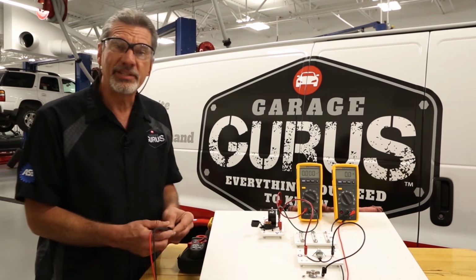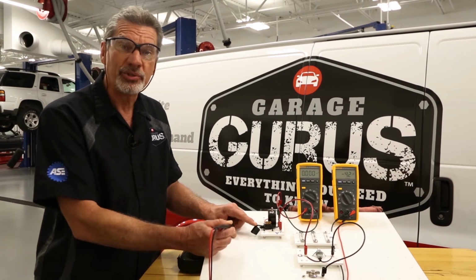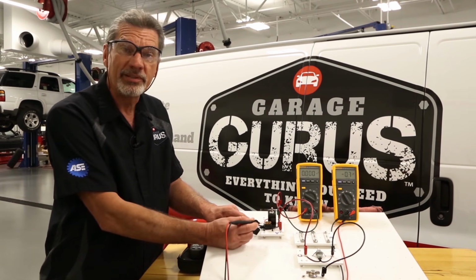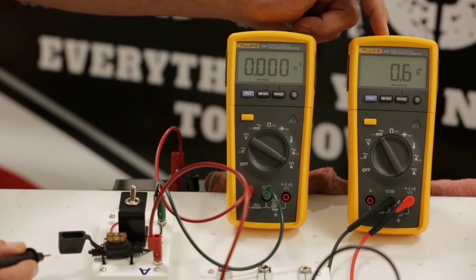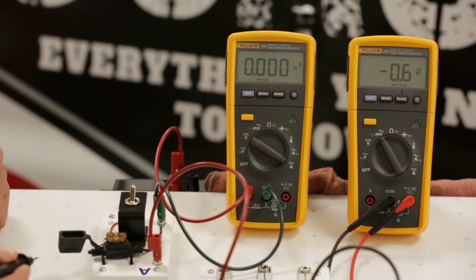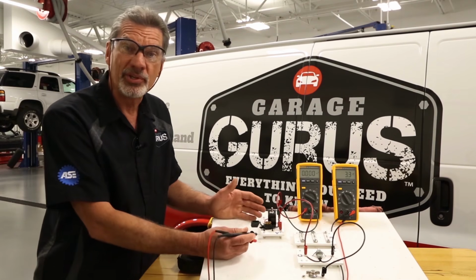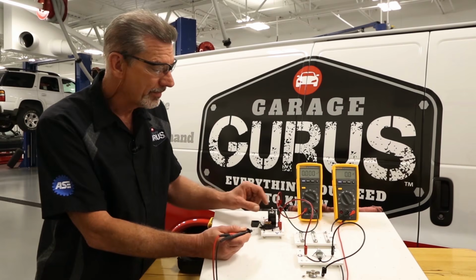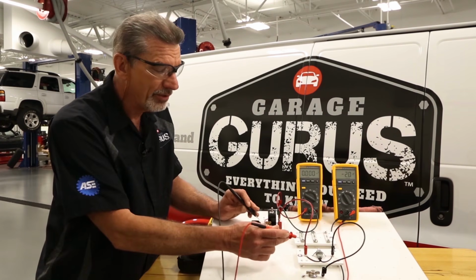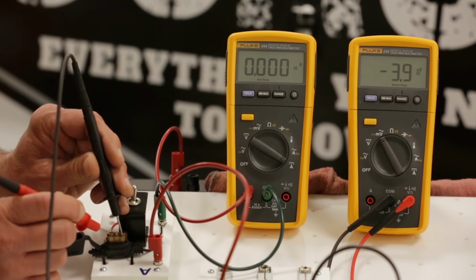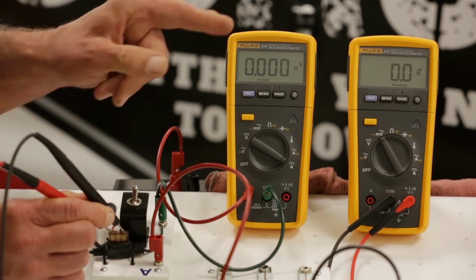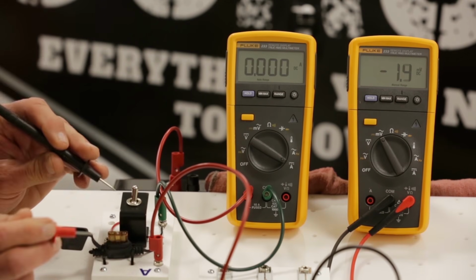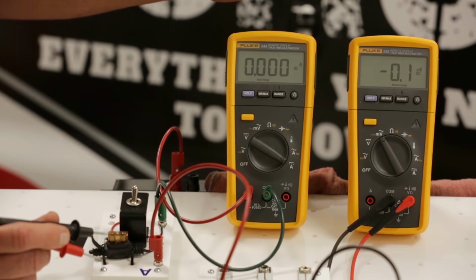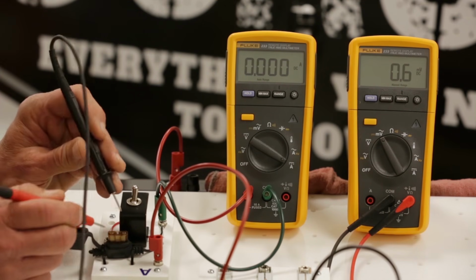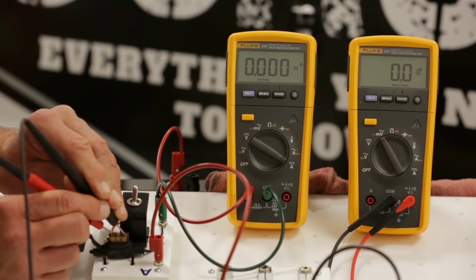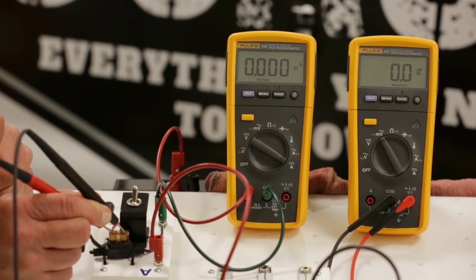So what this technique consists of is measuring the voltage drop across the fuse while it's still plugged in. The meter on the right is reading voltage, the one on the left reads amperage. I've set up just a simple circuit on this electrical diagnosis board, and with no current flowing through the circuit, if I measure voltage across the fuse, the meter goes to zero. With it disconnected, you show a small transient voltage that just has to do with the internal circuits of the meter. But connected to a fuse with no current, you show dead zero.